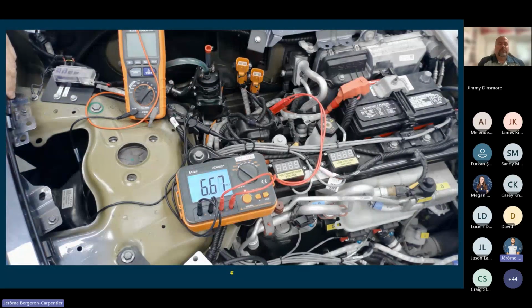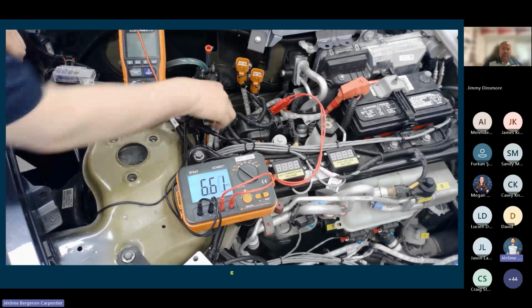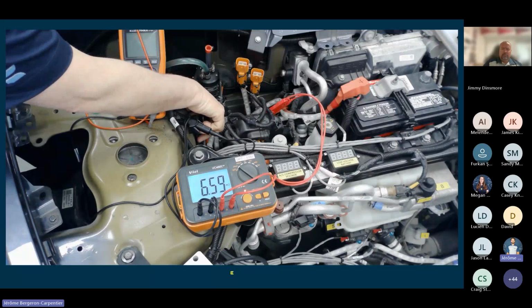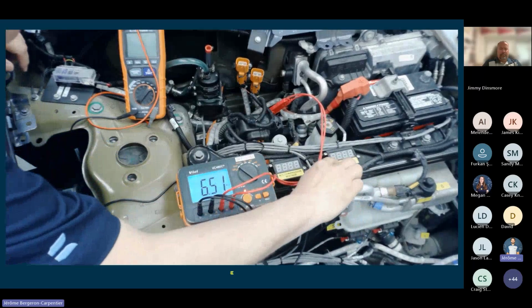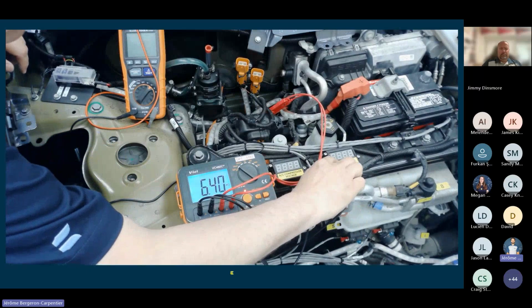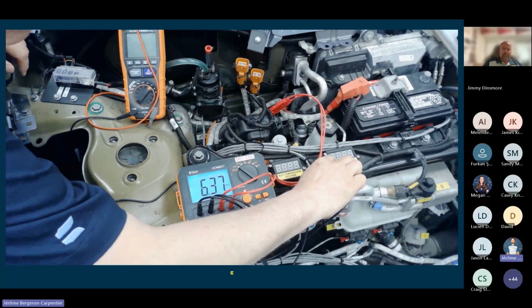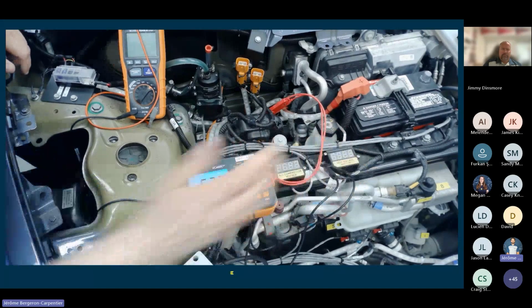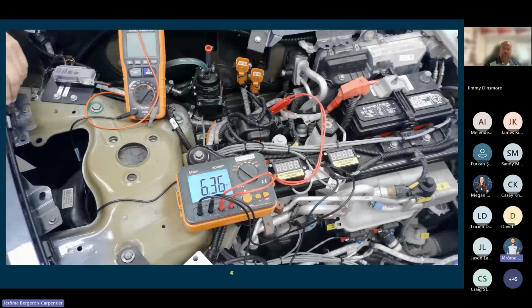6.77. The manufacturers do have specifications, we call it equipotential bond testing, usually done on high voltage batteries, but it can also be done on components as well. Once I have that, I stabilize the number, 6.6 milliohms, and then I can go to another component here, and I got about the same, probably less than about 2 milliohms or 0.2 milliohms. So well within specifications. Some manufacturers are 1 milliohm. So we're well within that spec.